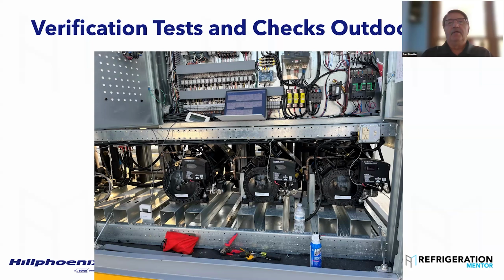Yep. Something else I want to hit on while we're talking about the startup is the pressure testing for the system. Everybody's used to, we're going to start up an HFC rack, we're going to take it up to 150, 200 pounds, and it's good. Well, with CO2 racks, there's a greater step. Your low temp is pressure tested to 350. Your medium temp pressure tested to 500. The discharge piping is tested to 1400 psi.